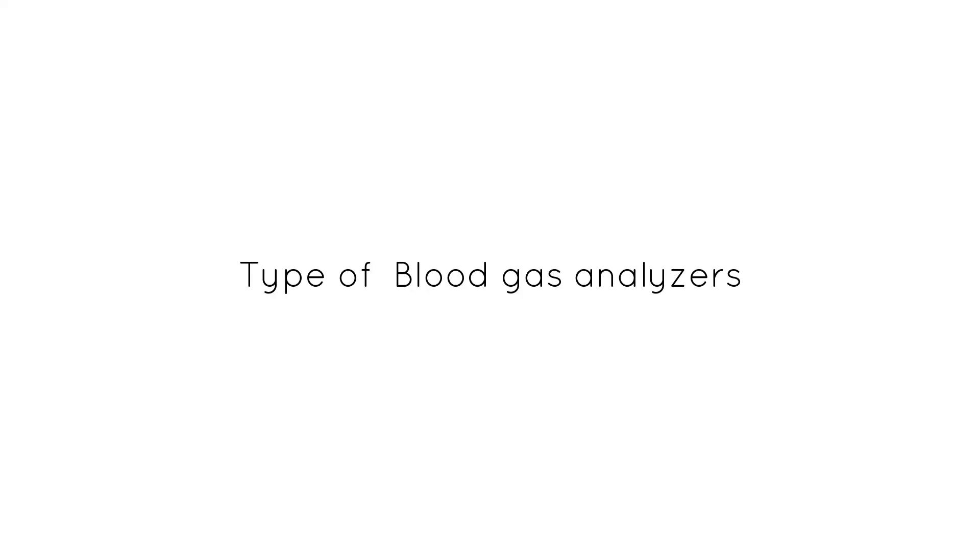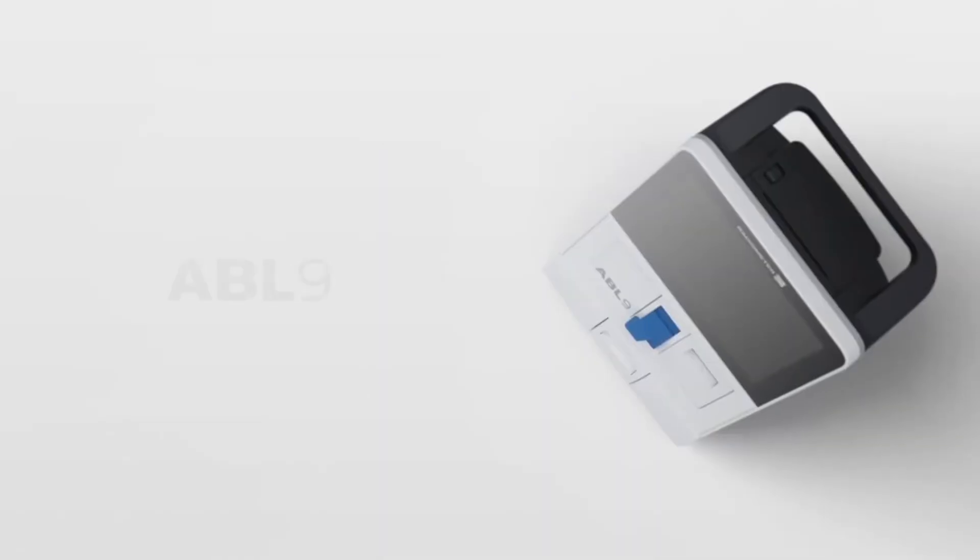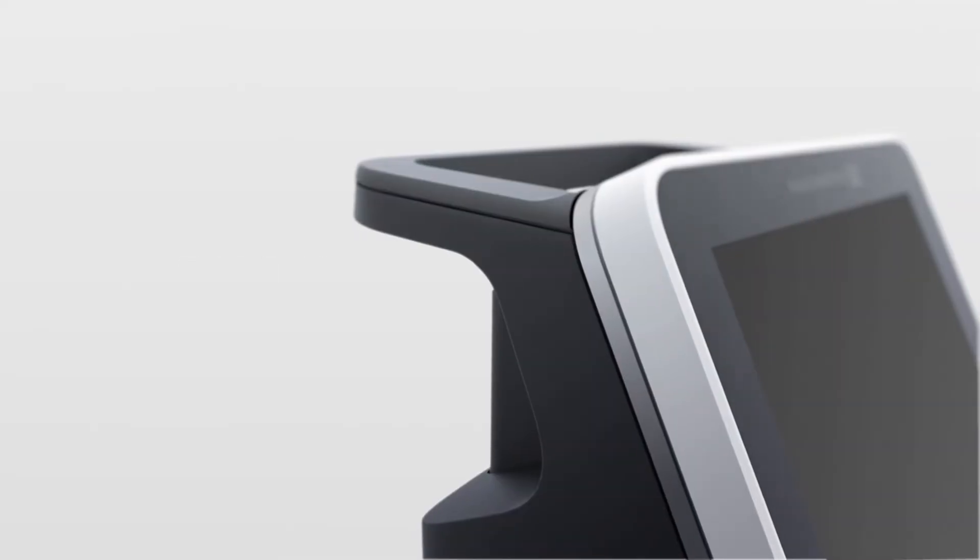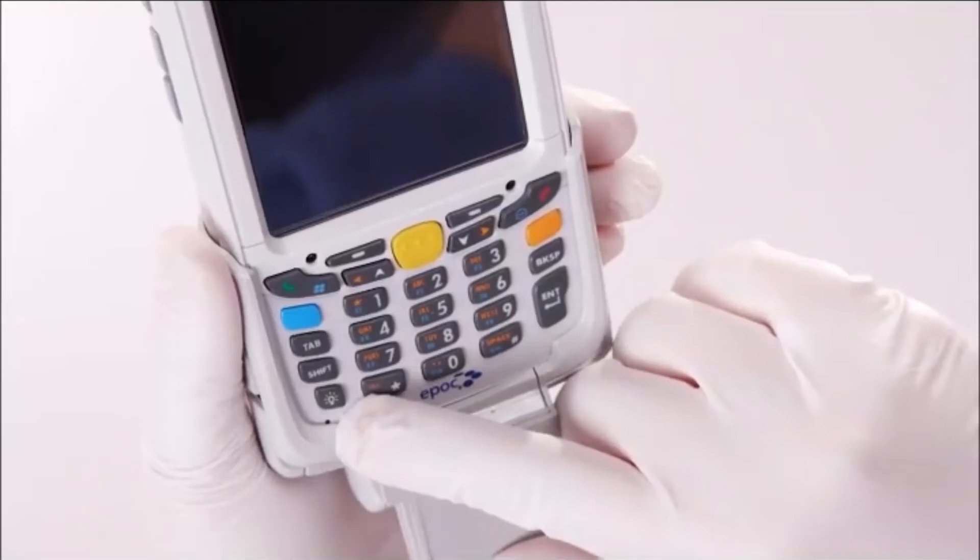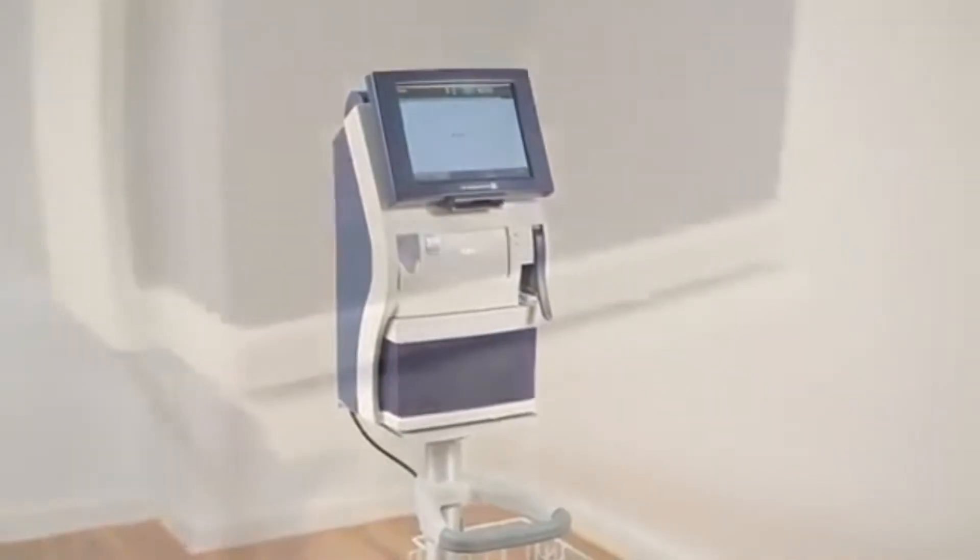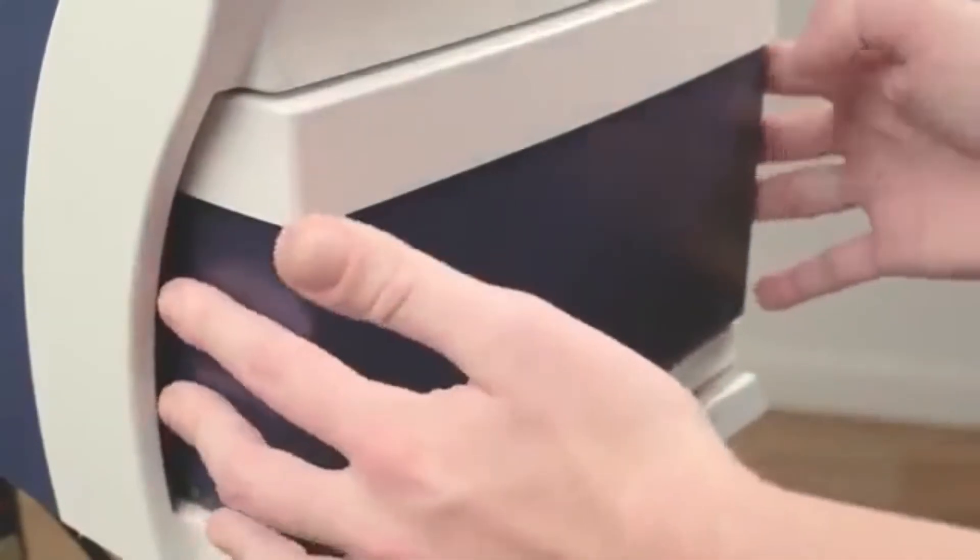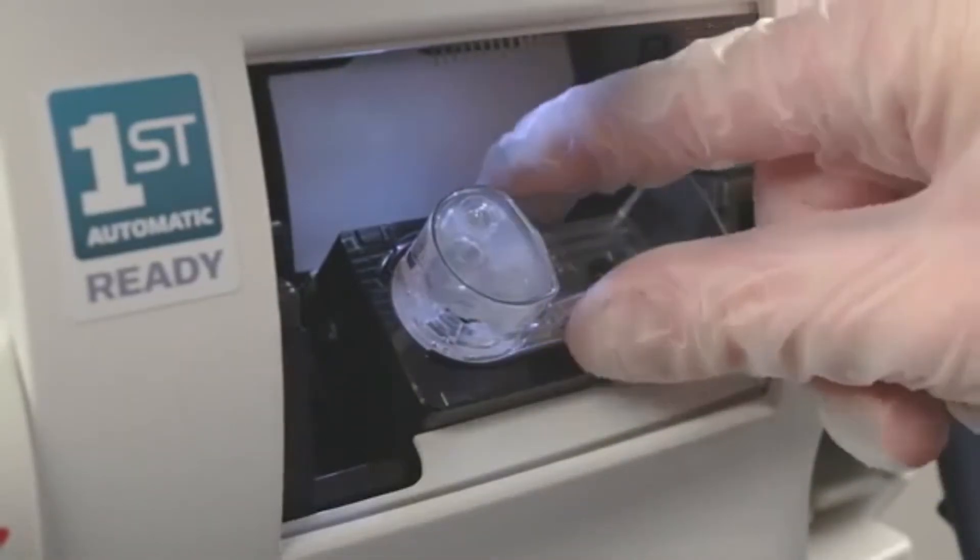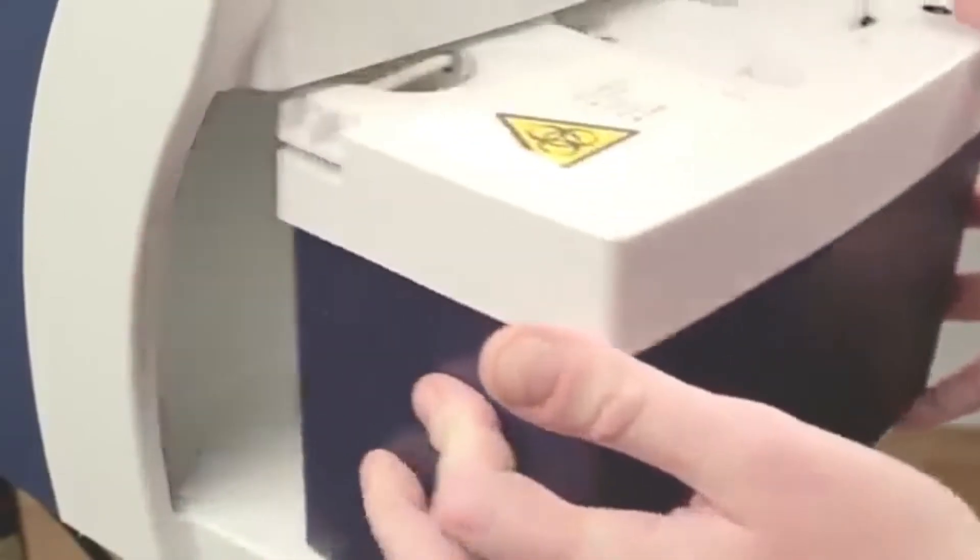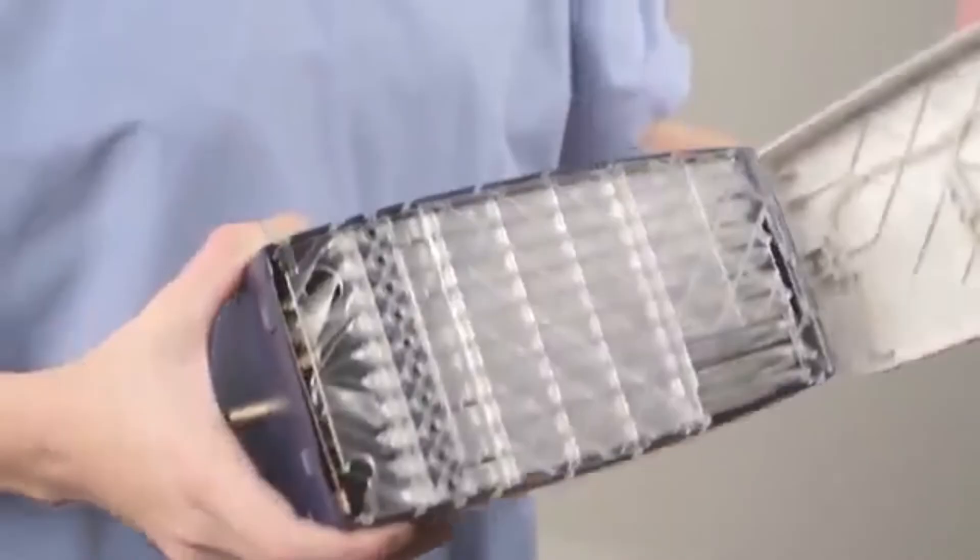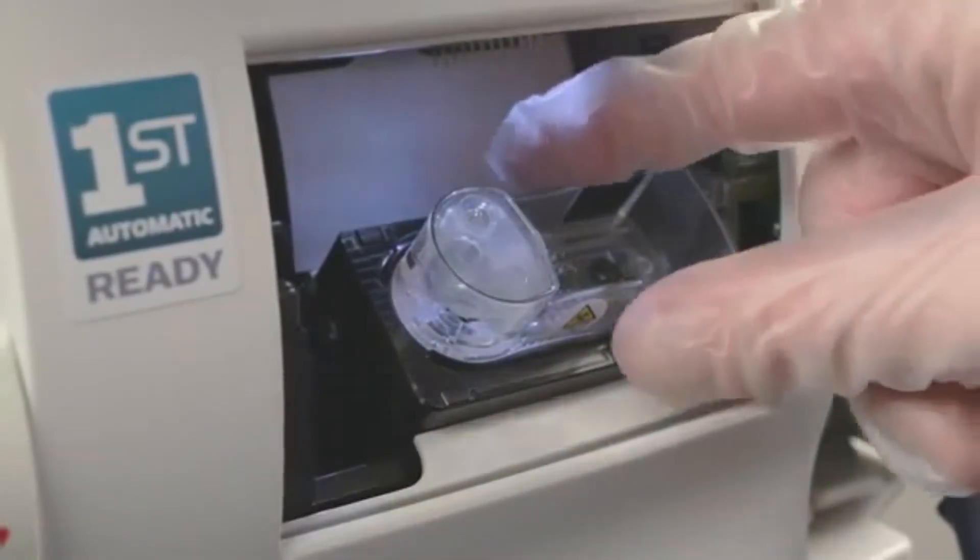Let's look into the types of blood gas analyzers. There are two major types of ABG analyzers available in the market. One is a standalone conventional ABG analyzer and the second is a portable ABG analyzer. First, let's look into the standalone ABG analyzers. In a standalone ABG analyzer, the machine consists of two major things: the reagents pack and the sensor cassette. Reagent packs provide necessary reagents to measure the ABG values along with mixing blood samples. The sensor cassettes have all the electrodes which calculate the values of different parameters in blood.